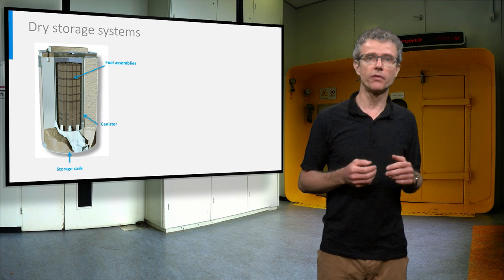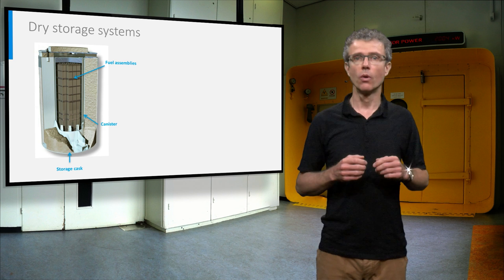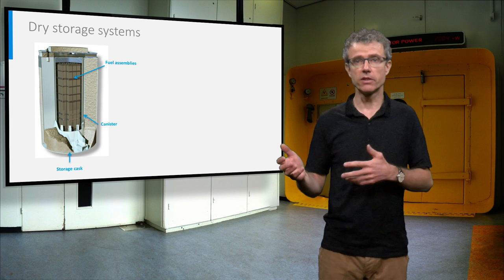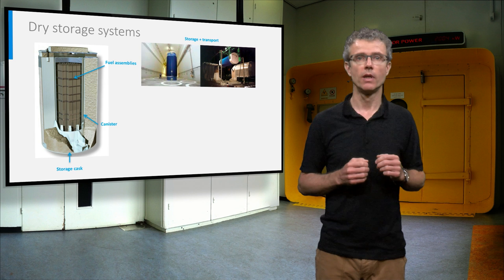Other countries put the spent nuclear fuel after sufficient wet cooling in dry storage containers. Whole spent nuclear fuel assemblies are placed in a welded or bolted canister under inert atmosphere. The canister is placed in a storage cask, or in a transportation cask, or in a dual-purpose cask, combining both purposes.